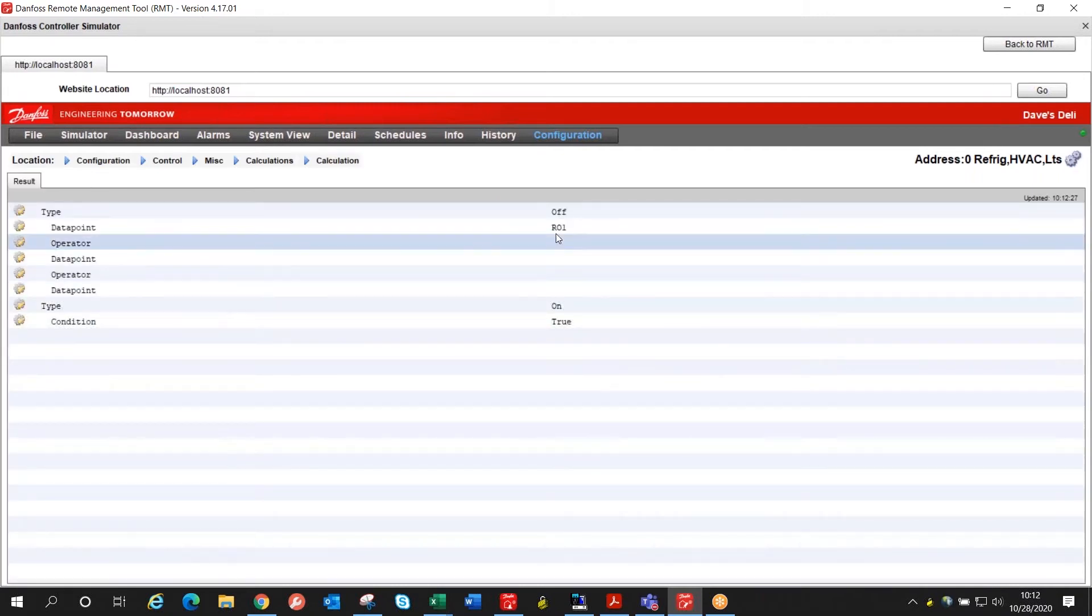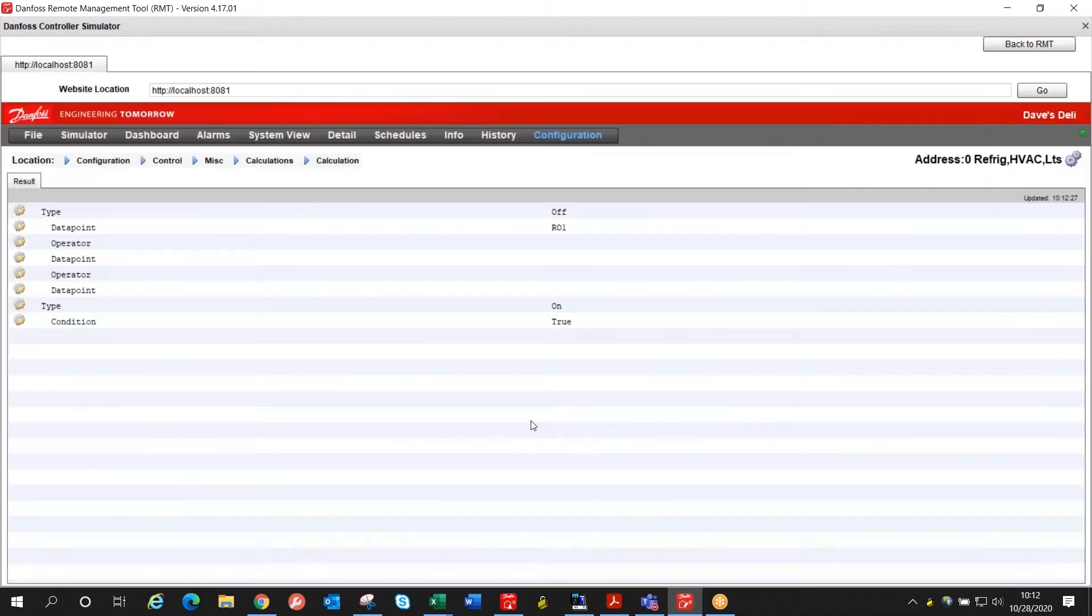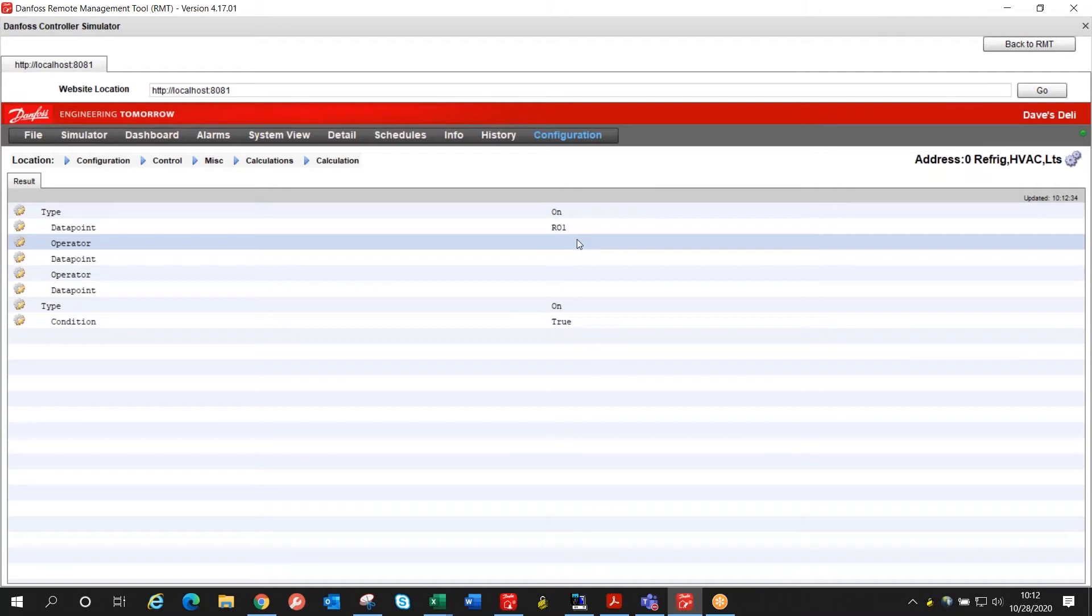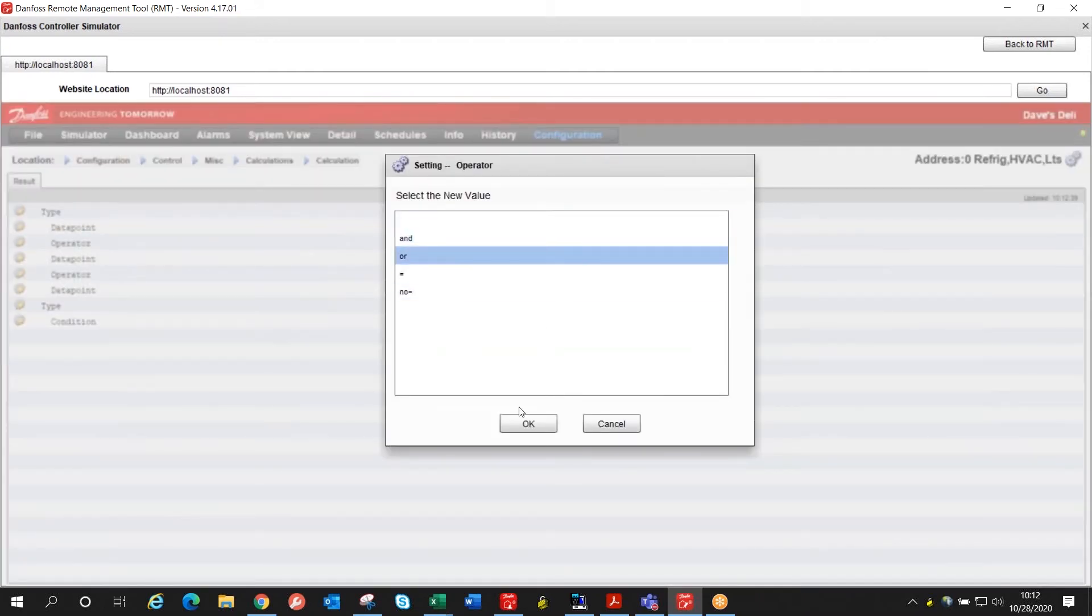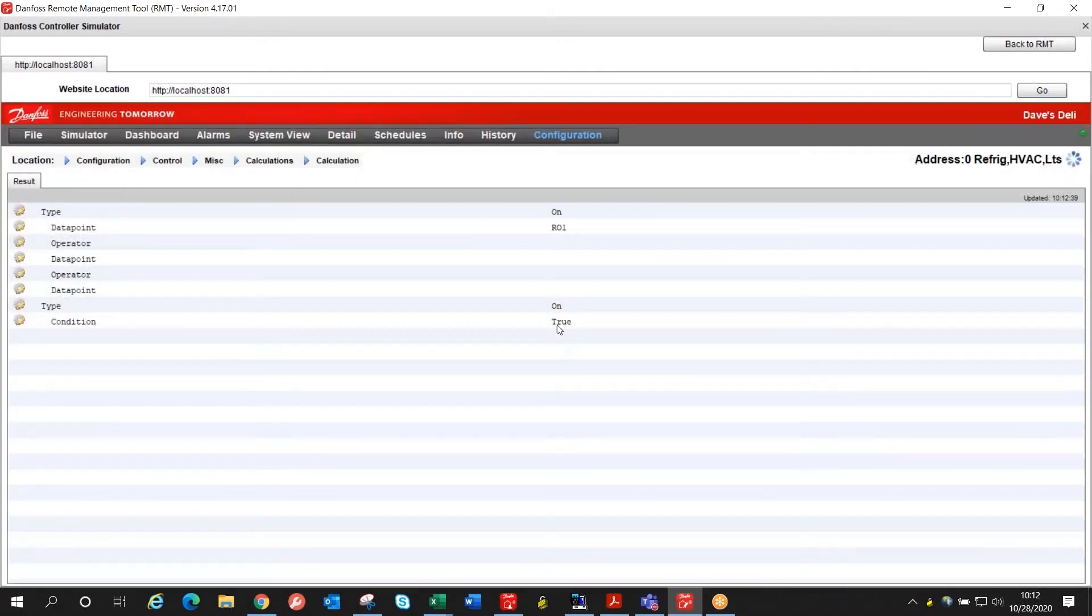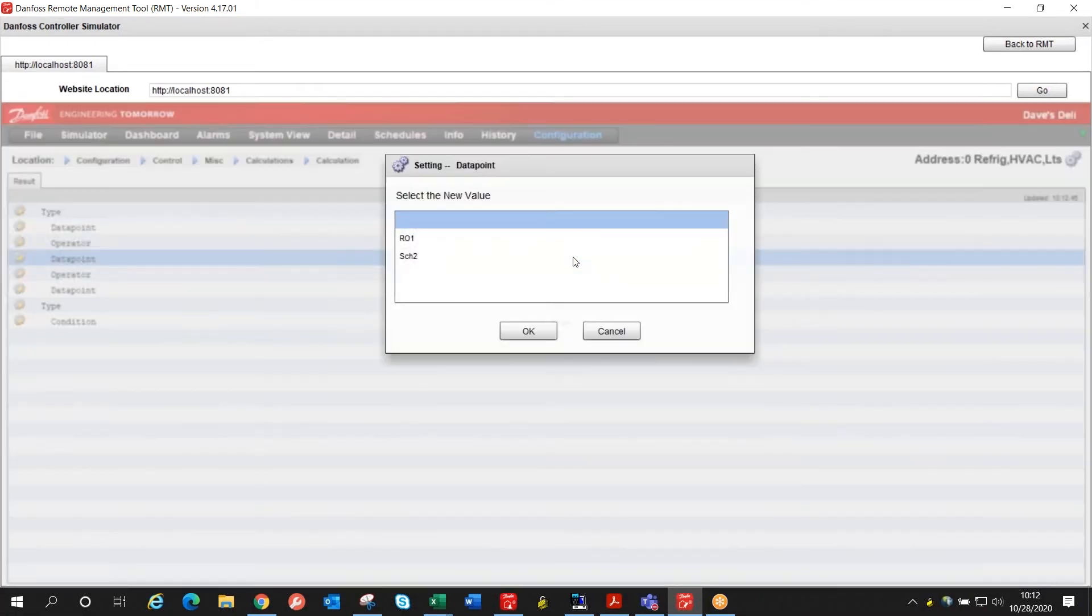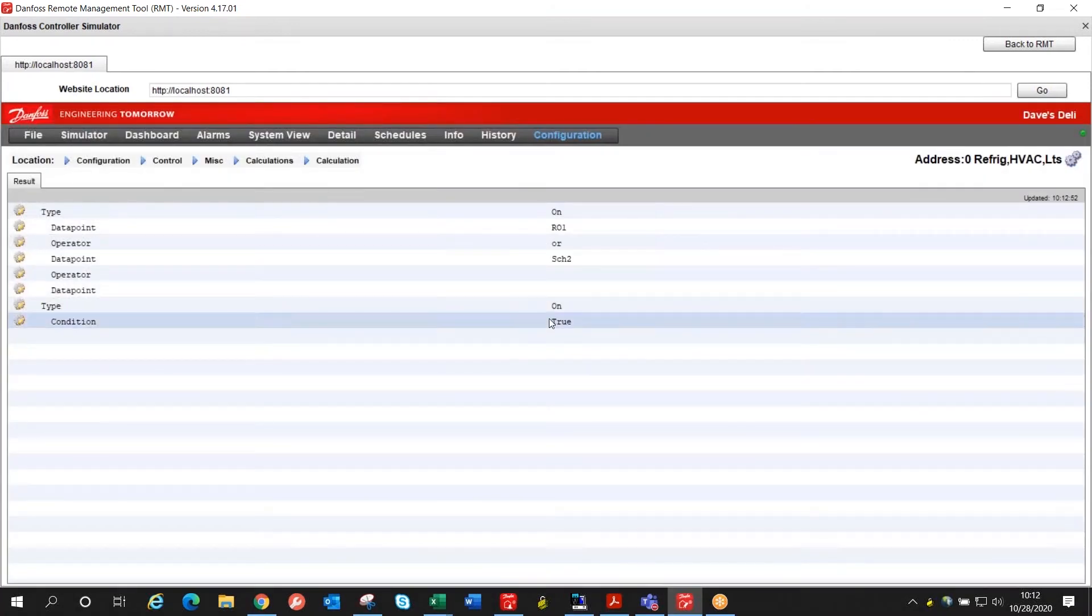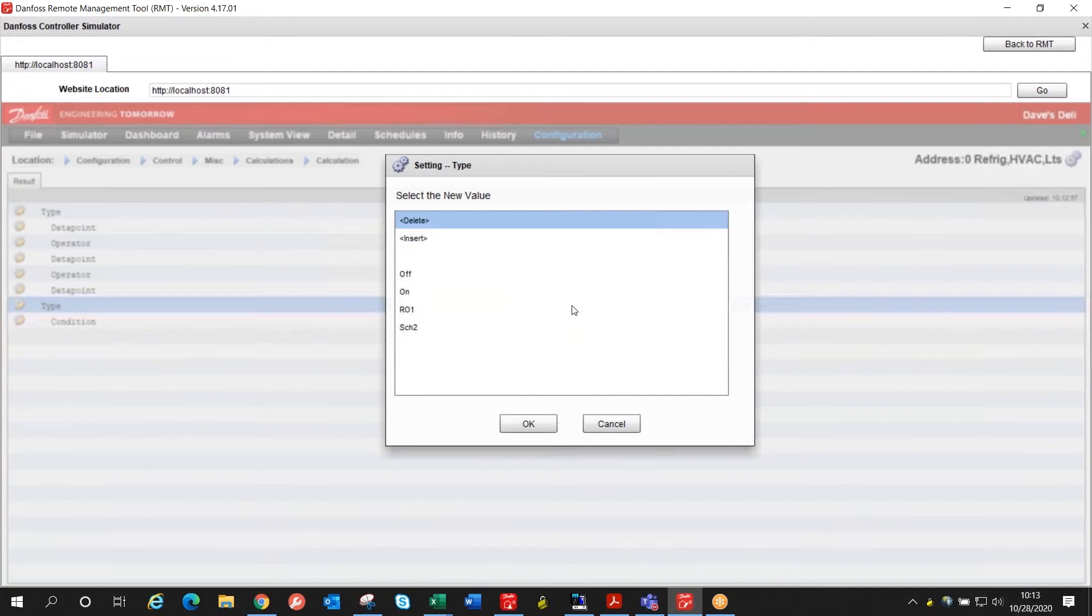This line will be changed to be our on option for the compressor and we're going to tell the calculation we want it to be on if that compressor is running under the rack operation or the schedule happens to be true and that'll be from 7 till 7:10 in the morning. We're also going to tell it that if the compressor is not running under the rack and the schedule is not true that that compressor is allowed to be off.